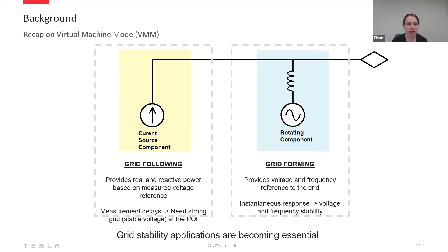I'll now spend a moment talking about the works we did in order to get approval for this virtual machine mode feature before diving into the commissioning activities themselves. As I pointed out in the earlier timeline slide, in order to build confidence around the machine feature, we needed to show how it responded to various grid events. Obviously, this is going to be pretty difficult in an actual grid connected installation because under normal network conditions, virtual machine mode is not really having any effect. It's really just running in the grid following element. So to demonstrate its operation we would need to see a real grid event, and it would take a very long time to observe all those scenarios that need to be shown on the network.